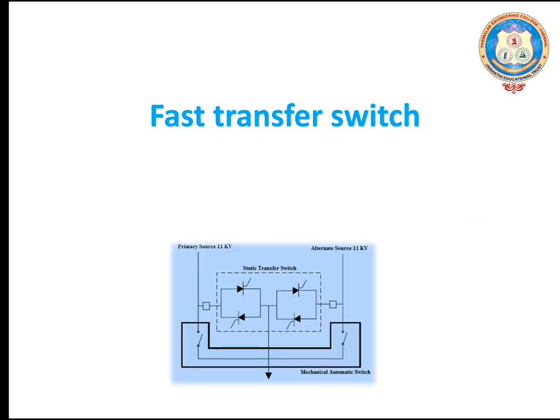What is a fast transfer switch? Fast transfer switches use vacuum breaker technology which can transfer in about two electrical cycles. This can be fast enough to protect many sensitive equipments.